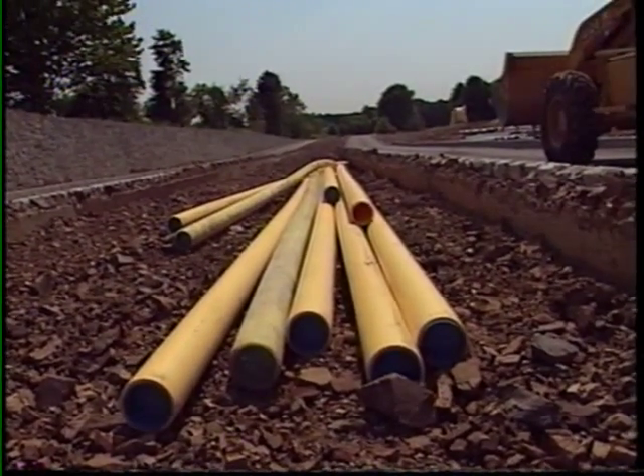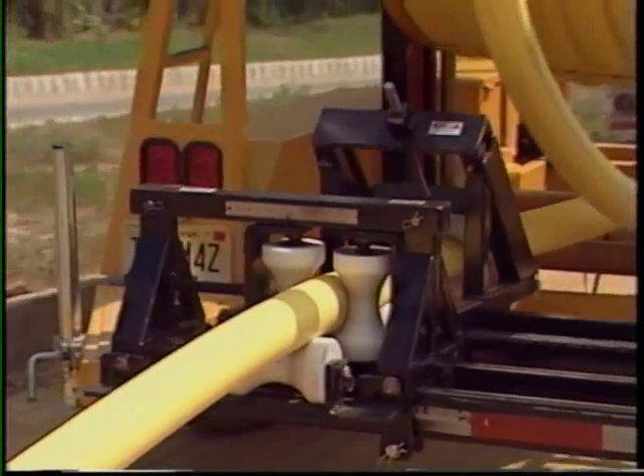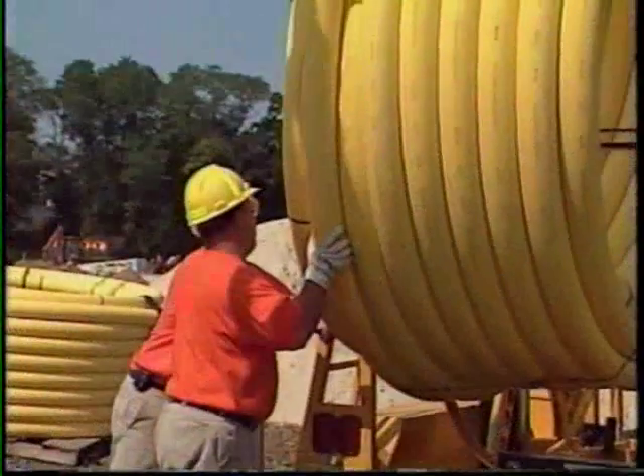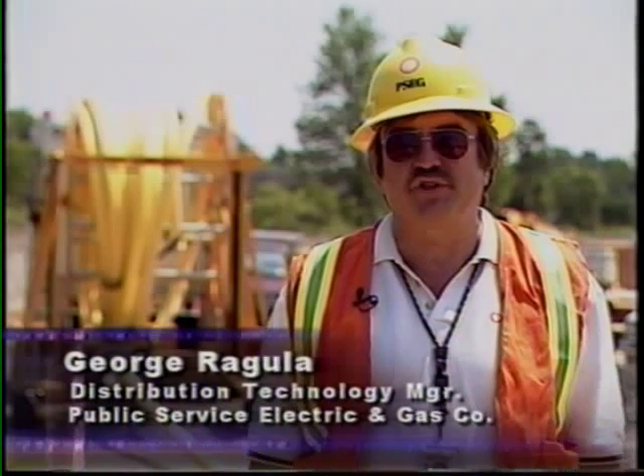The sticks are delivered to site by truck and then reassembled back into long lengths by fuse welding them together. This considerable waste of time and resources can now be avoided by purchasing the pipe in large coils. Using coil pipe with this trailer, a 1,000-foot run is completed with only two fused joints instead of 26.